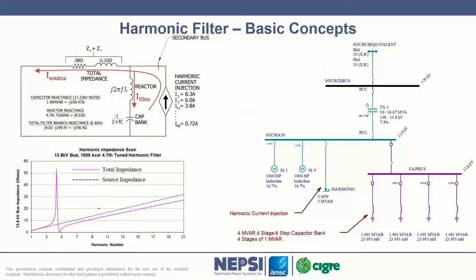But what I show here is the filter impedance. This is a 4.7 tune filter, and I also show the impedance of the source, that dashed line. That's this impedance here. And the amount of current at each and every harmonic is calculated by looking at the ratio of those impedances. It's an impedance divider. But you must pay attention to the fact that these are polar complex impedance quantities. They have a real component and a complex component.